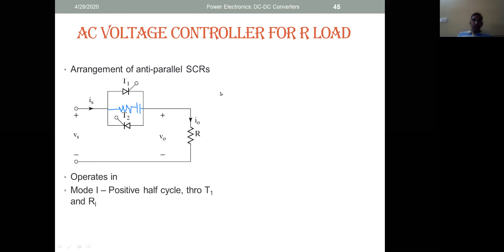Why are anti-parallel SCRs preferred? The natural reason is when one is conducting, the other is off. So it gets some cooling period and recovery of the device. If there is a single device like a triac, there is no cooling period and recovery is quite difficult. But a single device saves cost. So in some applications, it is preferred. So operation in mode 1 and mode 2, we discussed already. Another realization is a triac, a single device. It also needs a snubber across it.